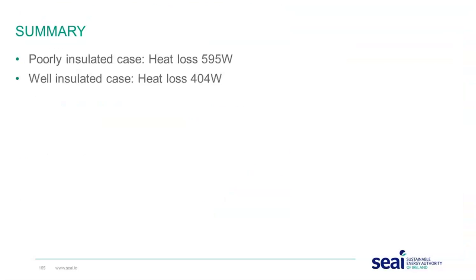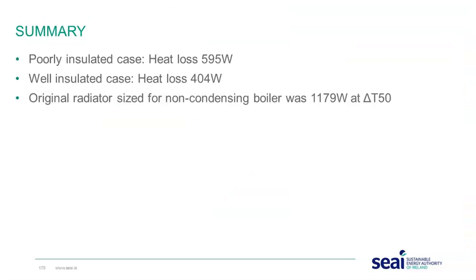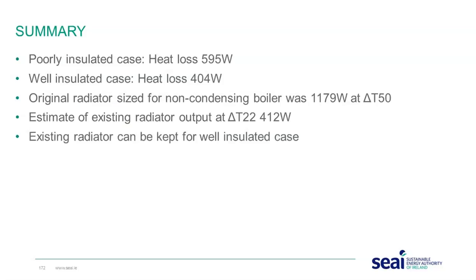So in summary over those ones there, in the poorly insulated case, the total heat loss for that room was 595 watts. In the well-insulated case, the heat loss was only 404 watts. The original radiator size for a non-condensing boiler was 1179 watts, and that was at a delta T of 50. So we need to estimate the existing output. That's at a delta T of 22, and we can see it's only 412 watts. So the existing radiator can be kept for the well-insulated case, but in the case of the poorly insulated, or relatively poorly insulated, bedroom, a new radiator is required.